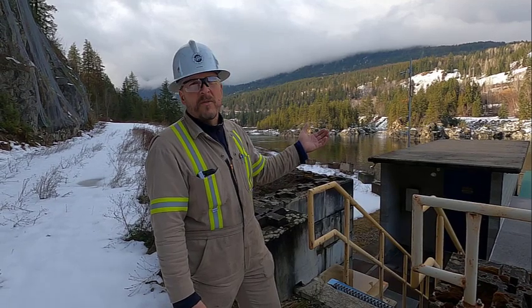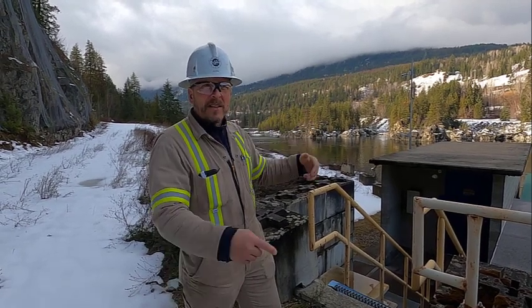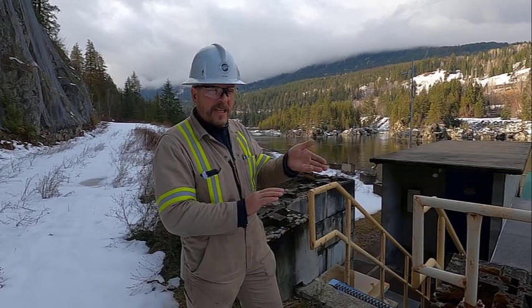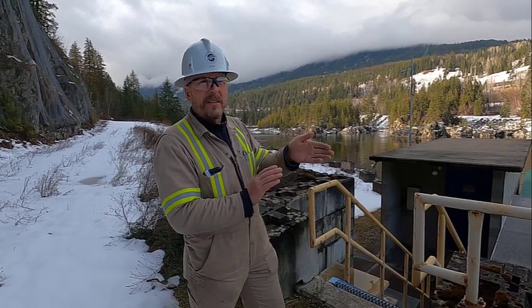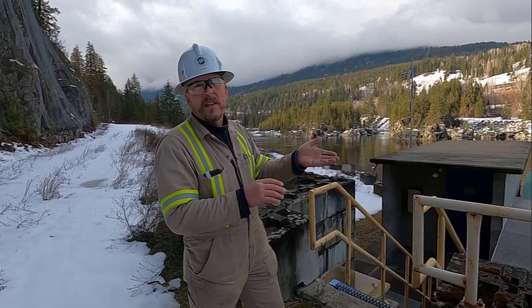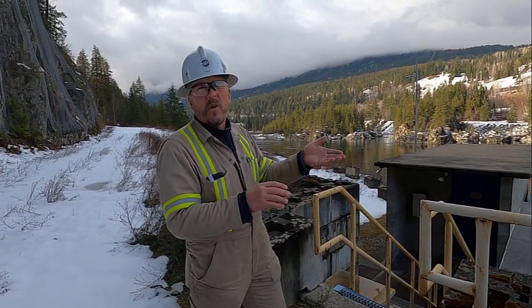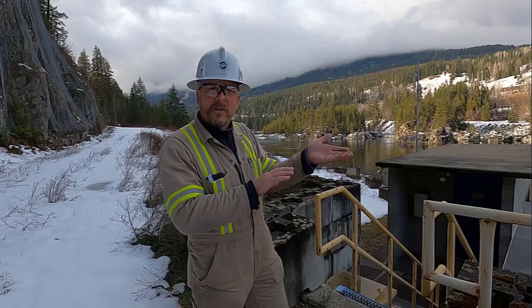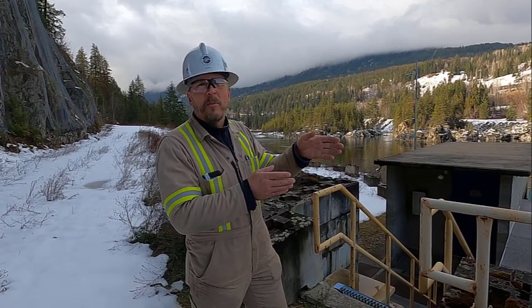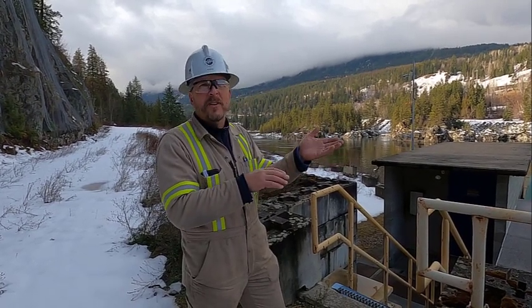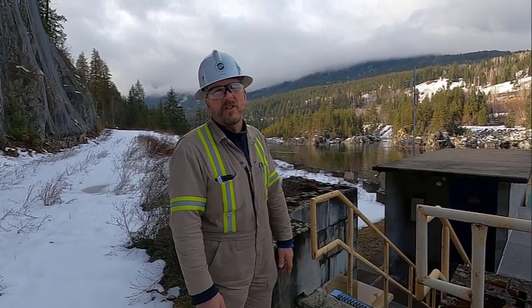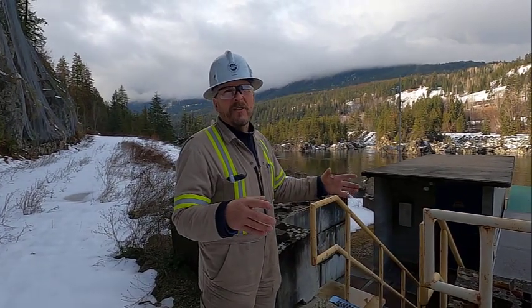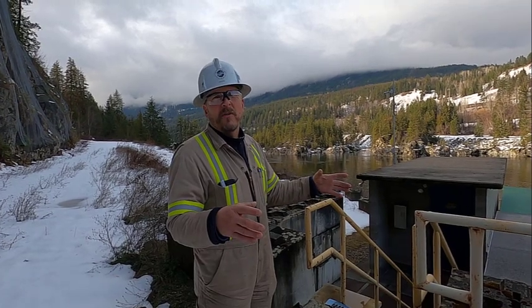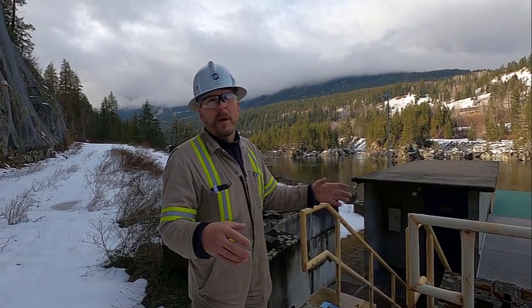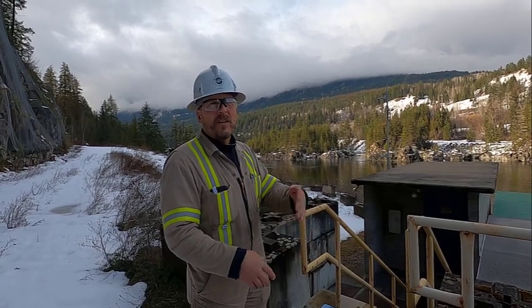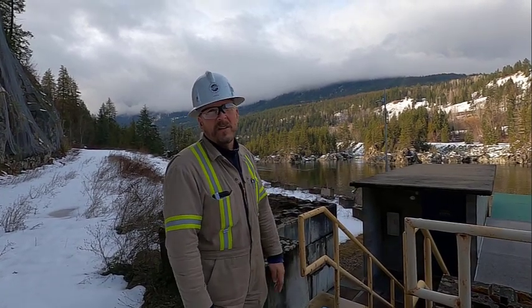It's just over 6 feet in diameter and it has 5 blades. Those blades all work in unison, and they change their pitch. If the unit's at a low loading, low power output, the blades go further flat, and at a higher output they go open, so it stays much more efficient. The other units are called Francis turbines, so they're designed for one fixed water flow, so you can't run them at a low power output as this unit can. So this unit has a lot more options for what loading you can use it at.